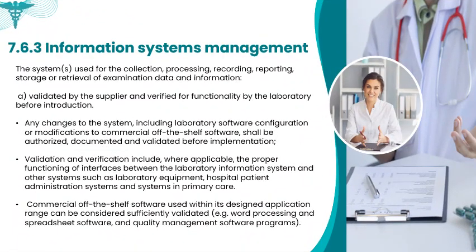Information systems management. The systems used for the collection, processing, recording, reporting, storage, or retrieval of examination data and information shall comply with the following requirements. Each system shall be validated by the supplier and subsequently verified by the laboratory for functionality prior to introduction into use. Any changes to the system, including software configuration within the laboratory or modifications to commercial off-the-shelf software, shall be authorized, documented, and validated prior to implementation.